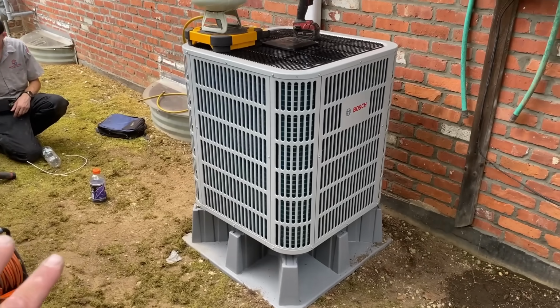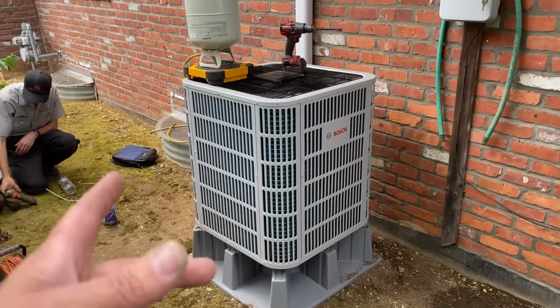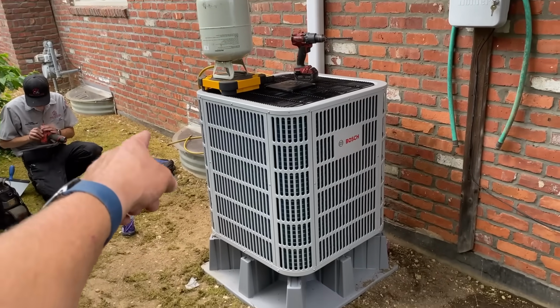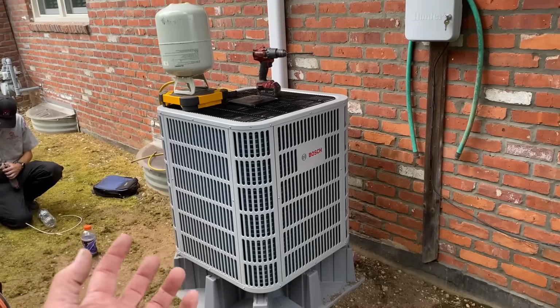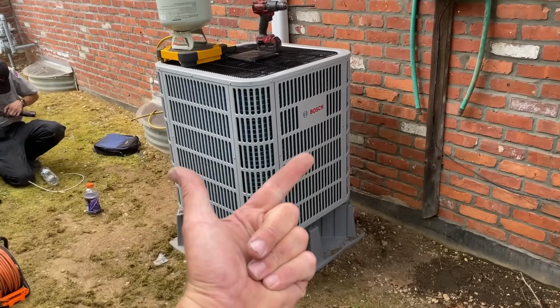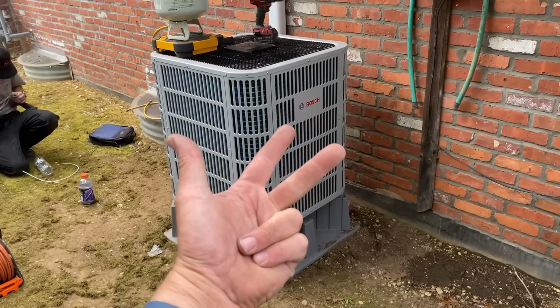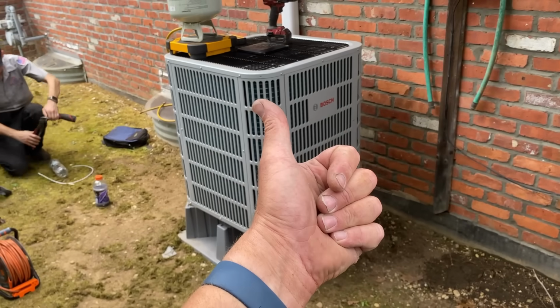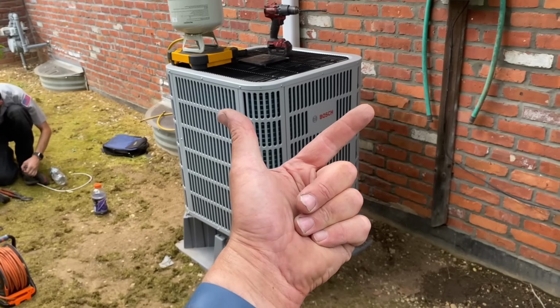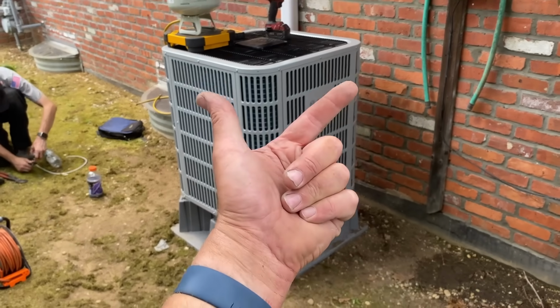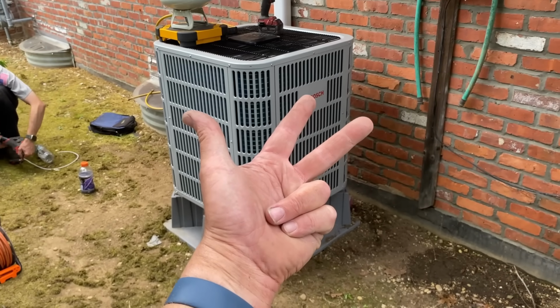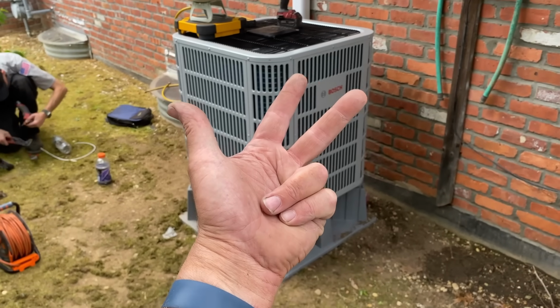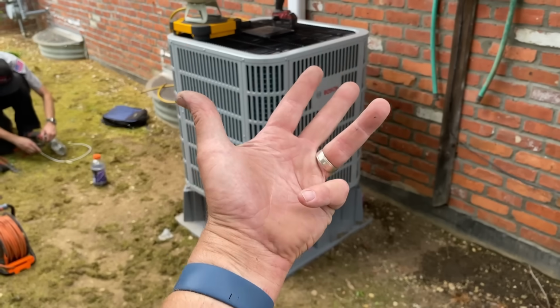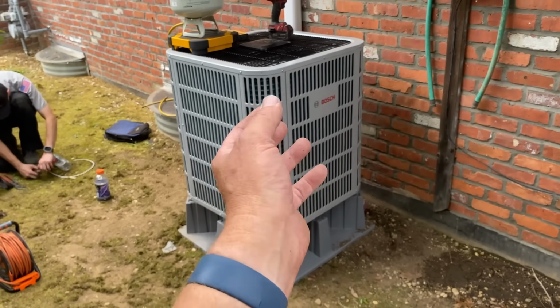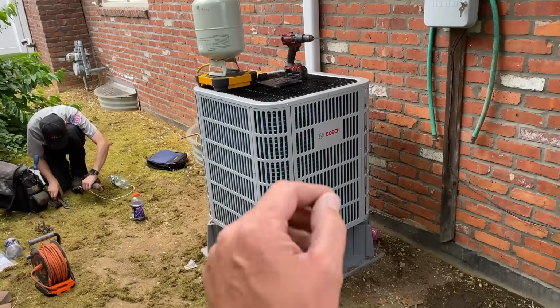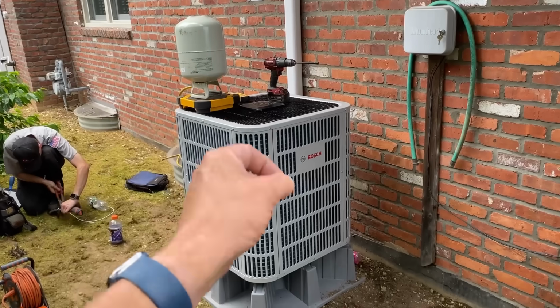And what we realized was that our Nest thermostat that was originally wired with 2 transformers, one for the hydronic boiler that's sitting downstairs in the basement to RH and W, and then the existing air handler, the one that we took out, we had RC, Y, and G. We removed that 3-wire, put in 5-wire with red for RC. We had a C, which we were not going to use for common, that we used for OB, for heat pump. And we had W, the white wire for Y2, second stage cooling. Yellow was first stage cooling, and G was our fan. And not having a common wire on this Nest, right, caused the problem. And what we did was we took out OB wire and made that common.